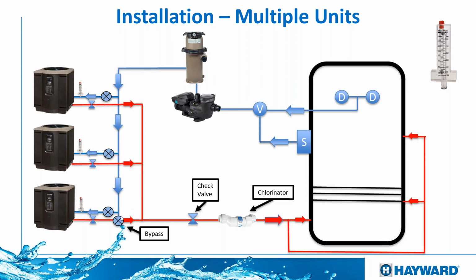At the end, over here at the bottom, we will have some kind of bypass in case we have too much flow for all 3 heaters in this scenario. Then we can open up the bypass so we can let some water flow without going through the heaters. Here you can see the red lines are the return lines from the heaters. That means hot water. They come all at the same side, and then they join to return the hot water to the pool.